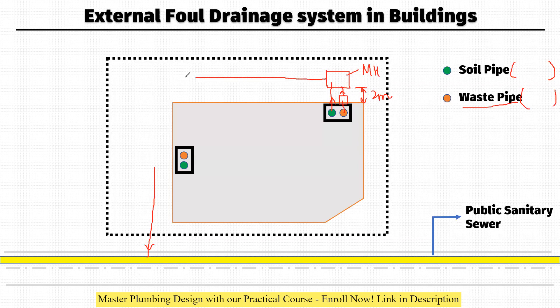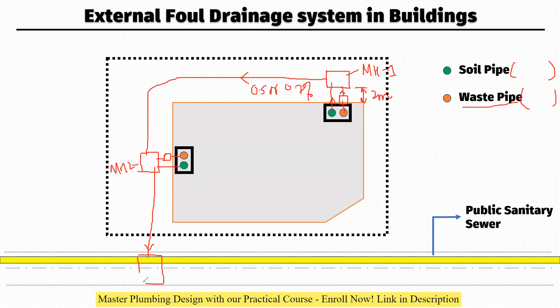A single pipe will be running from this manhole, and it will come here with a slope — generally 0.5% or 0.7%. We generally maintain less slope. The waste pipe connects to the gully trap, and from the gully trap it connects to the manhole. So this is manhole two and this is manhole one. From manhole two it will directly go to the public sanitary sewer.